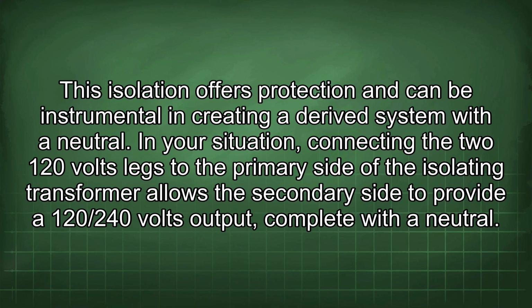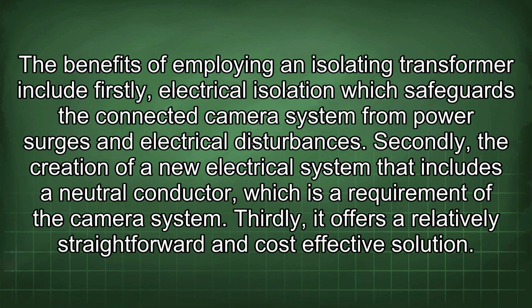In your situation, connecting the two 120-volt legs to the primary side of the isolating transformer allows the secondary side to provide a 120/240 volts output, complete with a neutral. The benefits of employing an isolating transformer include, firstly, electrical isolation, which safeguards the connected camera system from power surges and electrical disturbances. Secondly, the creation of a new electrical system that includes a neutral conductor, which is a requirement of the camera system. Thirdly, it offers a relatively straightforward and cost-effective solution.